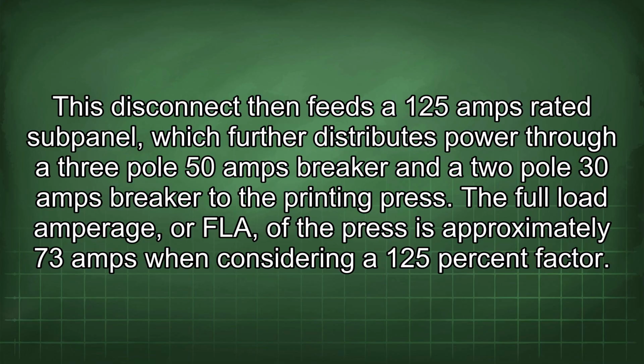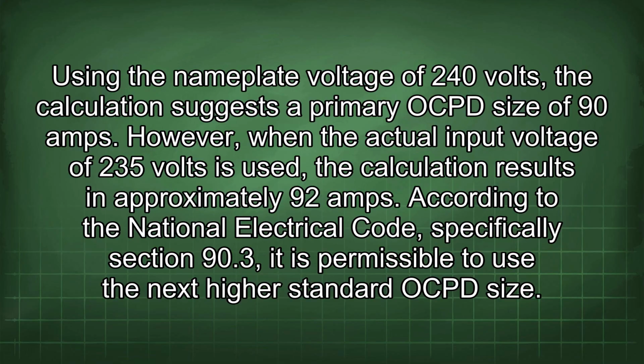The full load amperage, or FLA, of the press is approximately 73 amps when considering a 125% factor. Using the nameplate voltage of 240 volts, the calculation suggests a primary OCPD size of 90 amps. However, when the actual input voltage of 235 volts is used, the calculation results in approximately 92 amps.